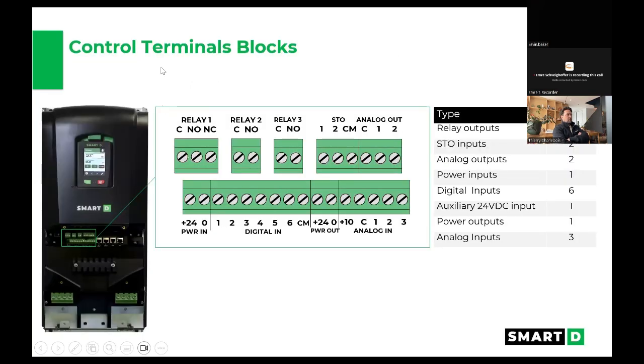For control, we've mimicked all the I/O that you normally get in some of the European brands out there, like a Schneider or a Vacon. So we've got the full 6 digital inputs. We've also got 2 STOs, 3 analog in, 2 analog out, and 3 relays for the 3 digital outputs as well, one of them being Form C.